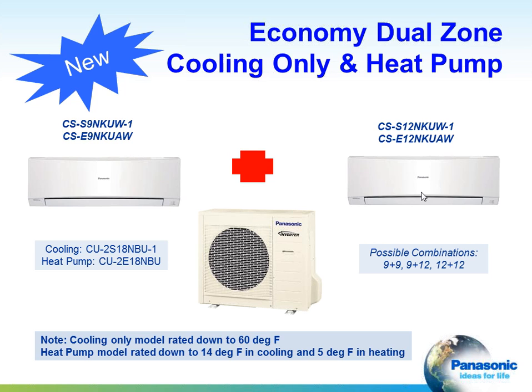We also have multi-zone systems as well. Here we're showing a 1.5 ton 2-zone unit with 2 9,000 BTU high walls. This will give you individual zoning in each space, and again, both in cooling only and in heat pump. This might provide an advantage over other brands because some of the other brands' multi-zone systems only come in heat pump. Cooling only will save a little bit of cost there. And this is not something you want to use in low ambient operation. It's meant for space cooling and space heating only.